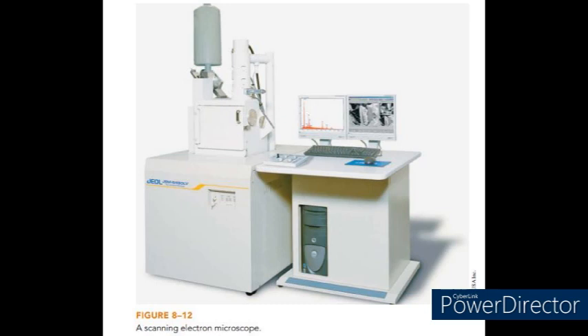The scanning electron microscope. All the microscopes described thus far use light coming off the specimen to produce a magnified image. The SEM is, however, a special case in the family of microscopes. The image is formed by aiming a beam of electrons onto the specimen and studying the electron emissions on a closed TV circuit. The beam of electrons is emitted from a hot tungsten filament and is focused by electromagnets onto the surface of the specimen. This primary electron beam causes the emission of electrons, known as secondary electrons, from the elements that make up the upper layers of the specimen.